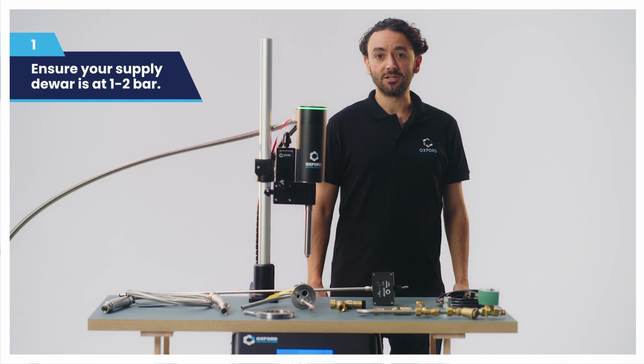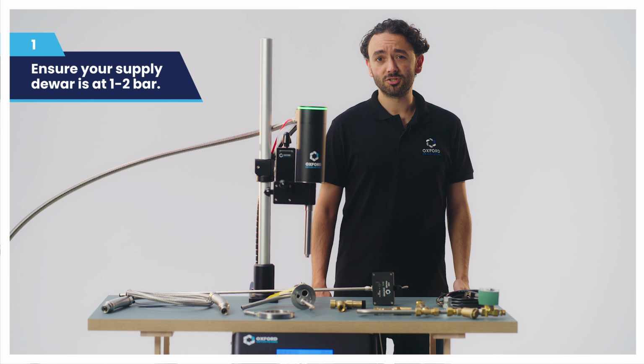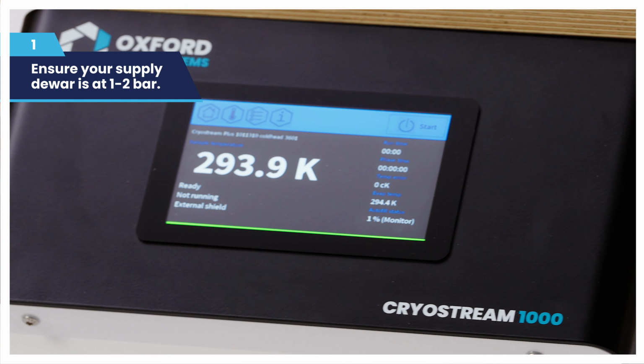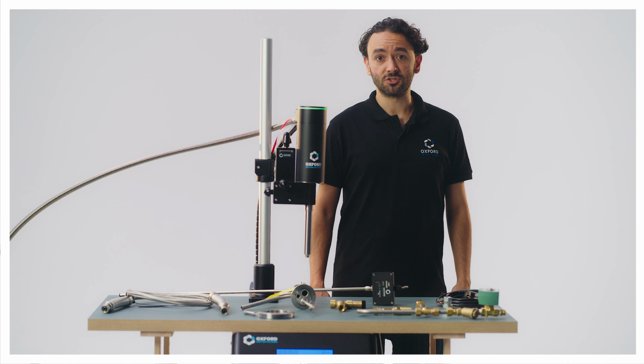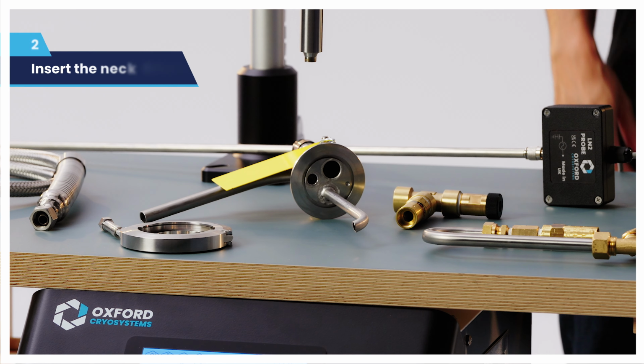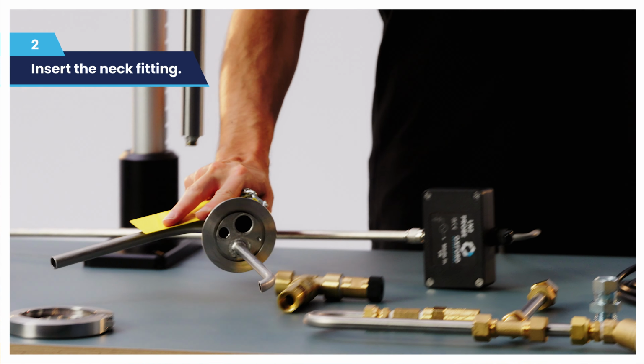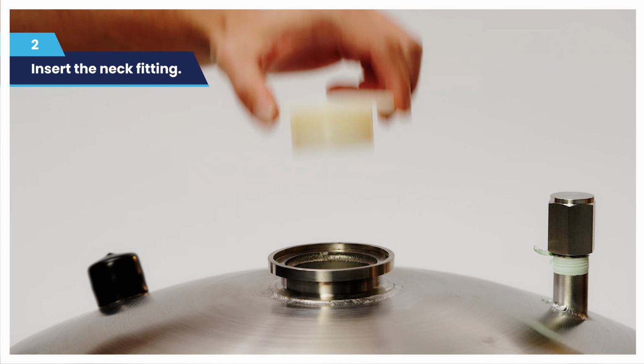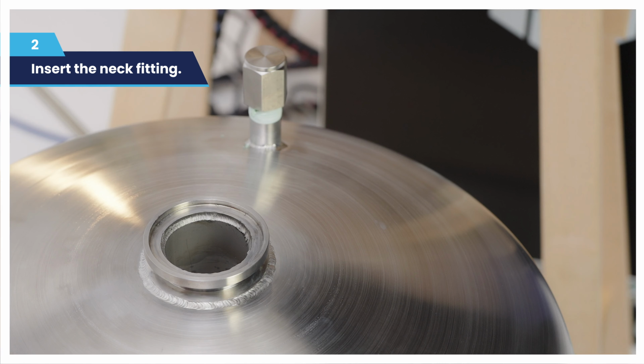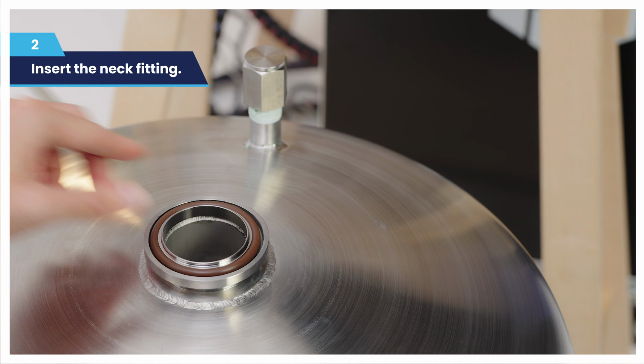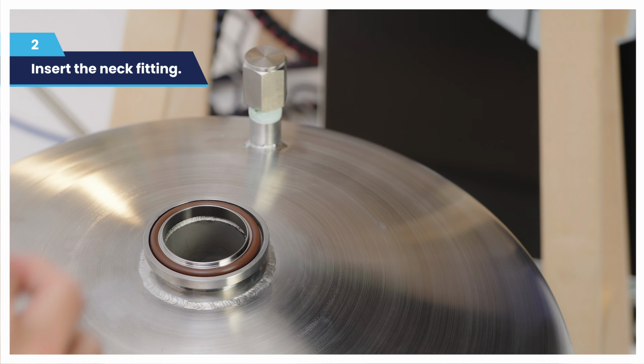Before setting up and using the Autofill, check the pressure of your supply dewar is between 1 and 2 bar. If the storage vessel has a pressure higher than this, the Autofill will not operate correctly. To install the neck fitting, remove the caps from the top of the dewar and place the sealing ring inside the dewar's opening. Now you can insert the neck fitting.